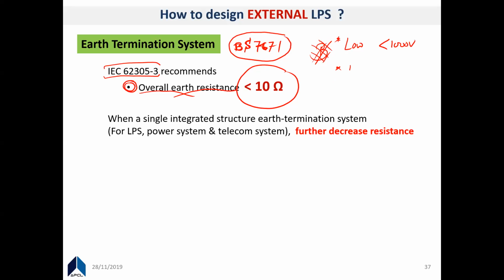Industrial. Okay, great, that's really great to hear, because there's no particular electrode resistance mentioned in BS 7671. It mentions about the loop resistance. So this is where you get the requirement of achieving earth electrode resistance of 10 ohms. It took a long time to discuss this point, because until the last moment, nobody answered.